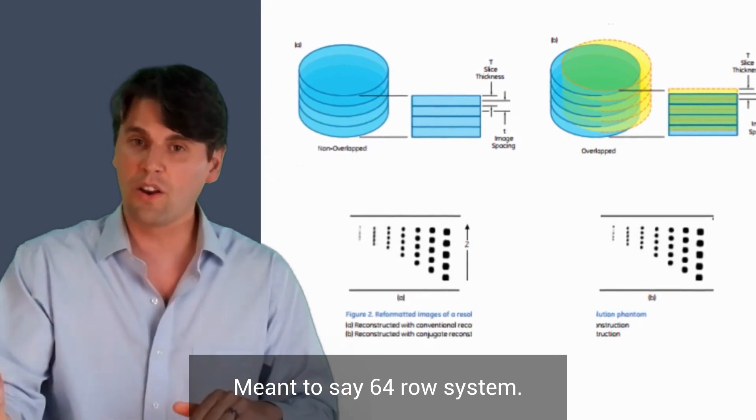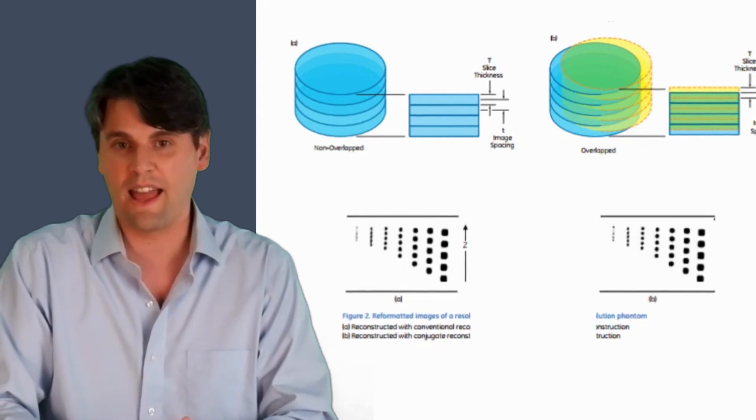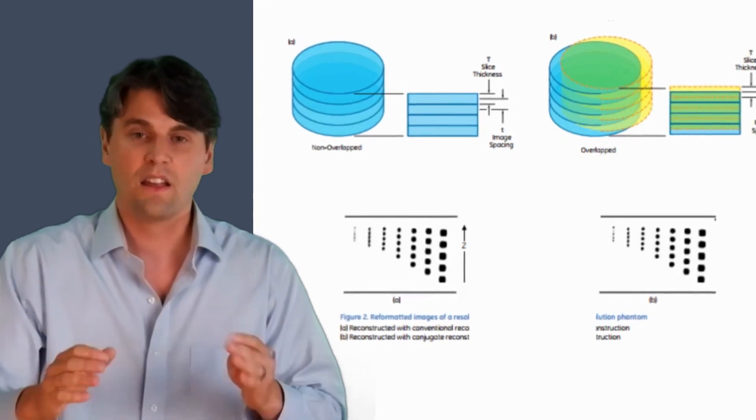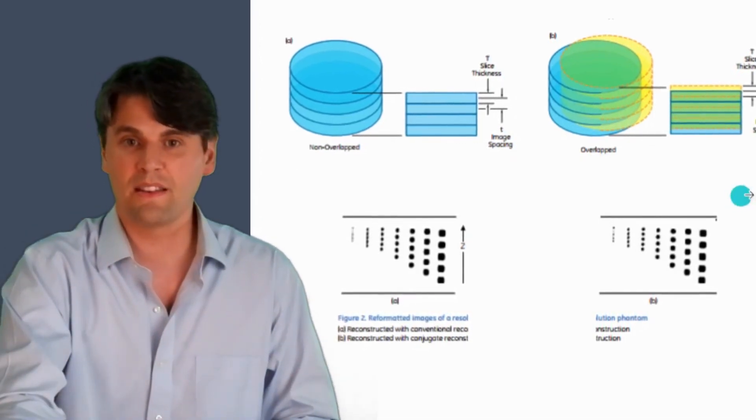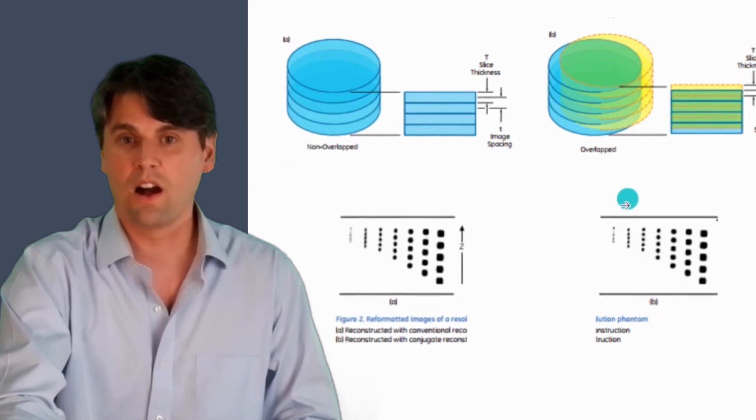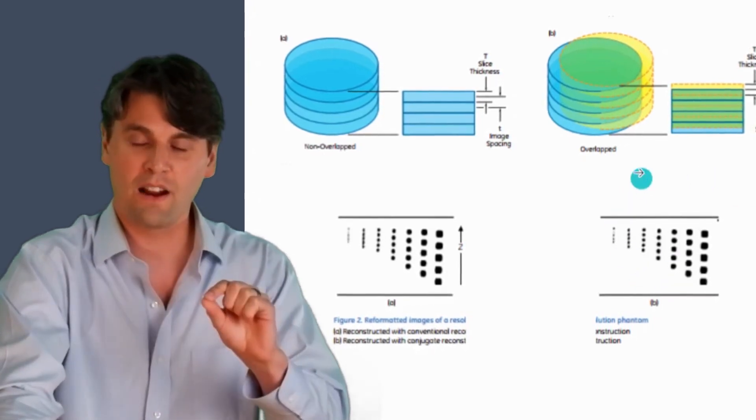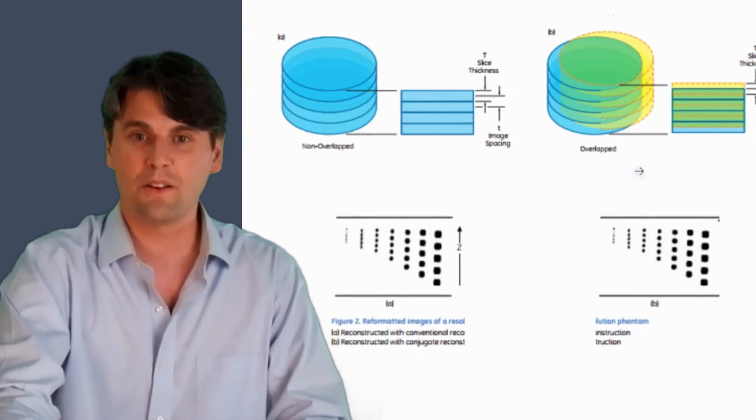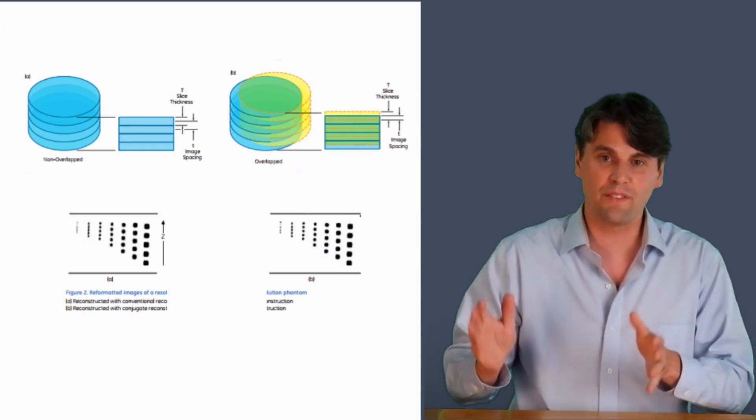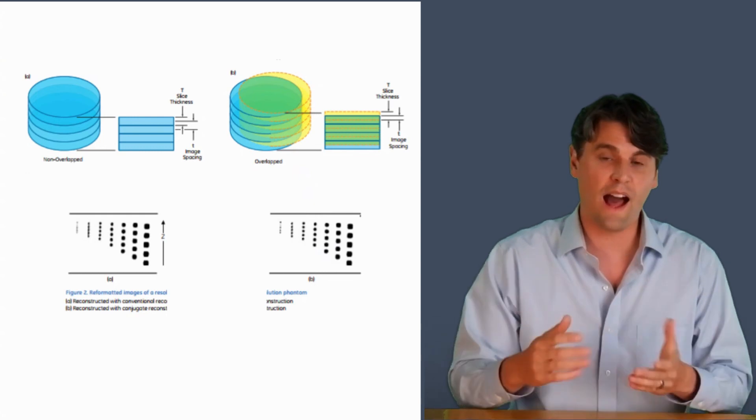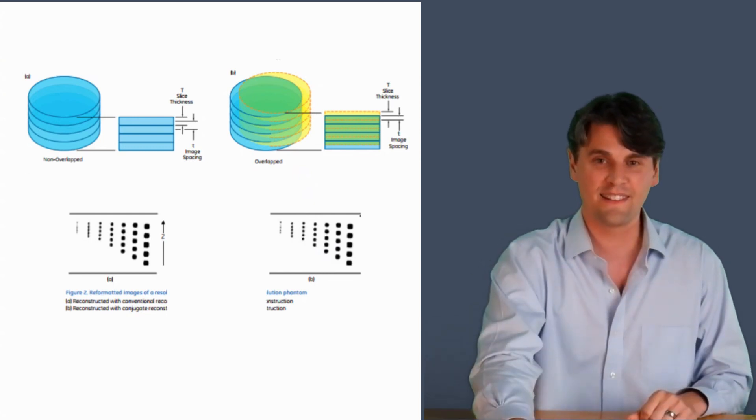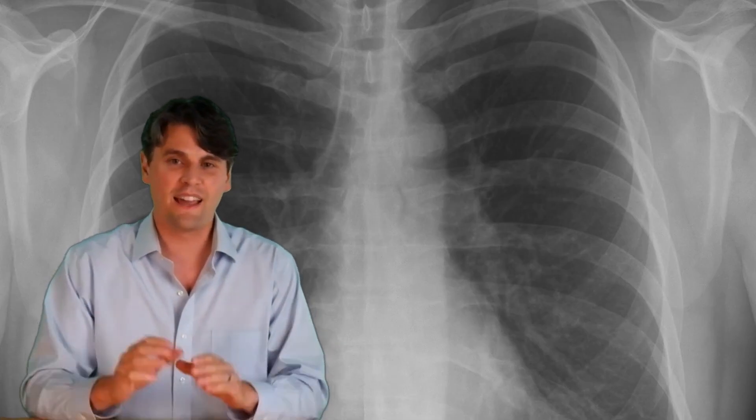So in that way, if you had a 64-slice system, then you would make 128 slices as you went around in an axial acquisition. And then you can see the improvement in the reconstruction of the different air regions inside of this phantom. You'll see improvements if you use focal spot deflection in the z-direction.